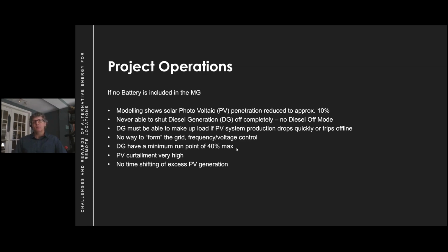Diesel generators have this 40% minimum run point, which really limits the amount of energy, especially in the summer, that is available left over for the grid, leading to very high PV curtailment. In the summer we have a community load of 150 kilowatts. The diesels are providing 100 kilowatts of that. The solar array can produce up to 300, but because it's a closed remote system, only 50 kilowatts is available, so we have to curtail that excess PV generation. It goes to waste basically.